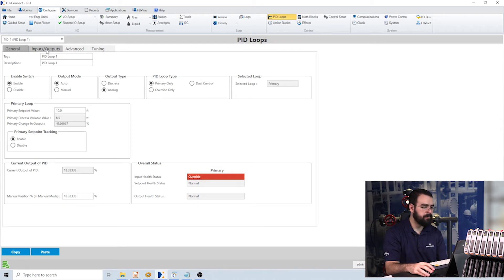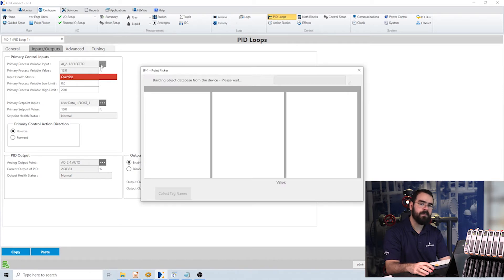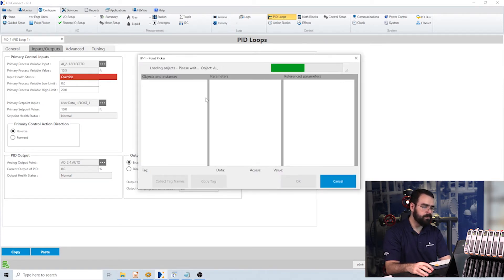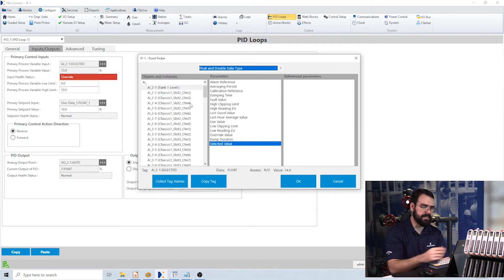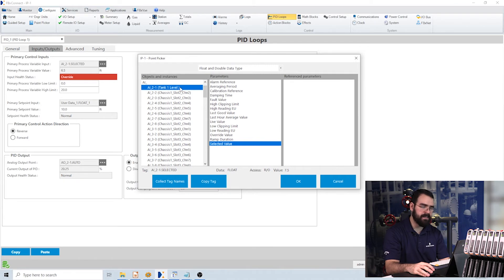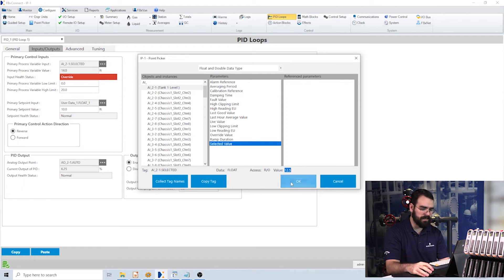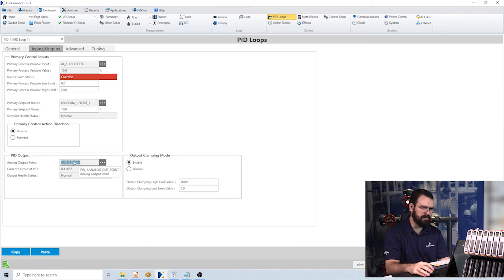Let's go to the Inputs and Outputs tab. Here's where I configure what values I'm using for my inputs and what point I'm using for my outputs. For each point, there's a three-dots button that opens a point picker, which allows me to find a point within my FB3000 database where all the data is held. For my input, I'm using an analog input point — I've selected the analog input object, opened it to see all instances, and for the selected instance I have a list of parameters, each with a tag, value, and data type. I'm reading the selected value parameter of analog input instance 2.1, which is that tank level I showed earlier. The current value is 7.5 — clicking again shows 12.5 because it's constantly being updated. I'm also reading the set point and writing to an analog output for this PID loop.